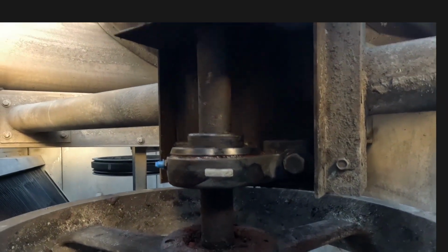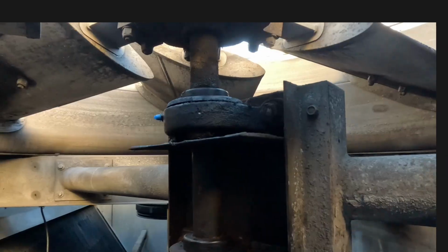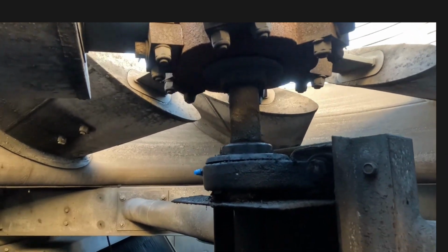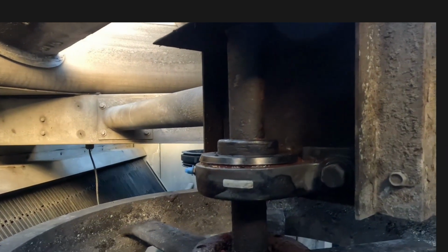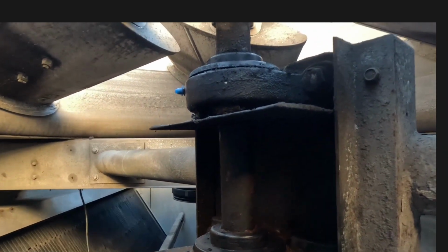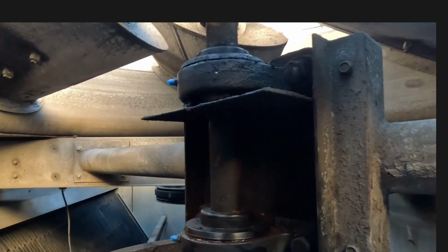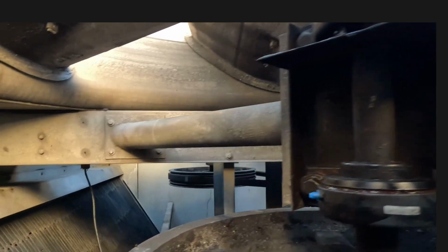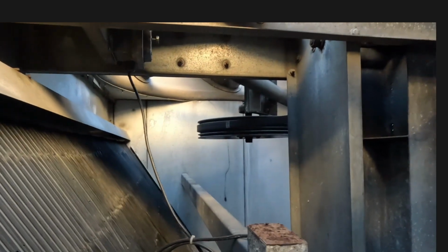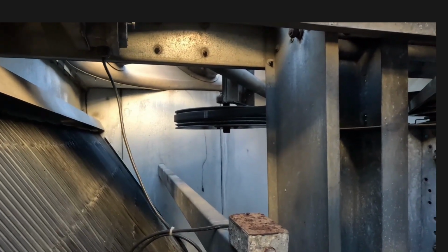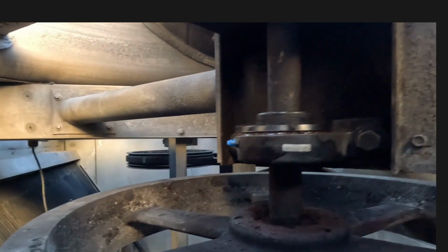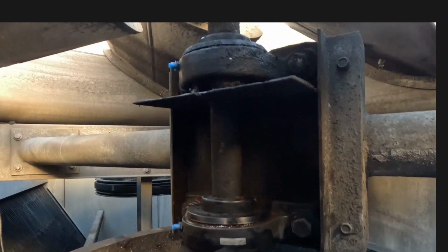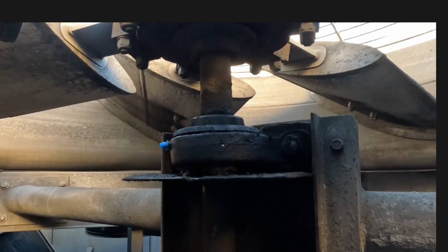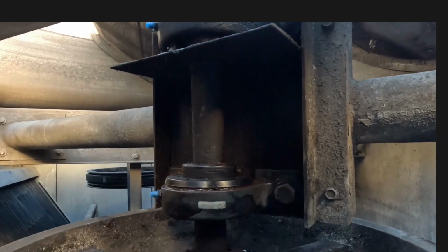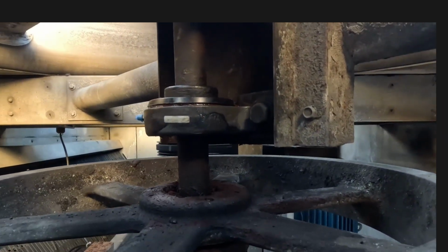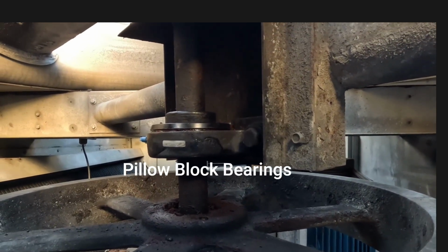He needs to replace that bearing there and that bearing there. But as you can see, it's a shaft from the fan assembly down to there. So luckily, I can run one cooling tower and have this one shut down while I replace the pulleys. And it's the same thing on the other. You got the same thing. You got two pulleys over there on that. So a total of four. I guess these would be called the pillow block bearings when we refer to them. If anybody has a better description of them, I would like to know. But as far as my knowledge, this is what we call them, the pillow block bearings.